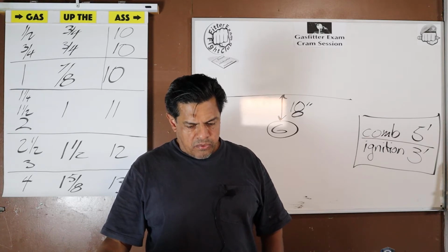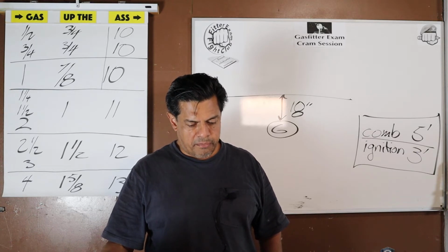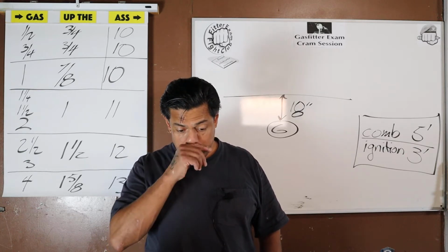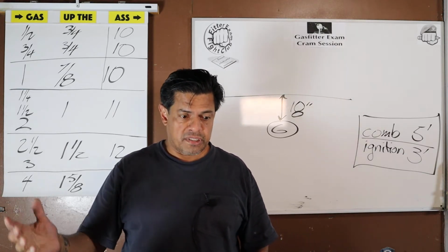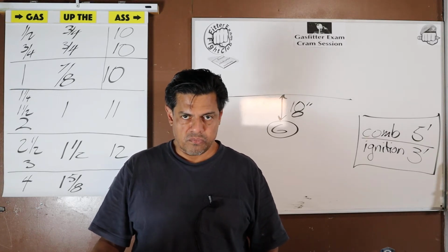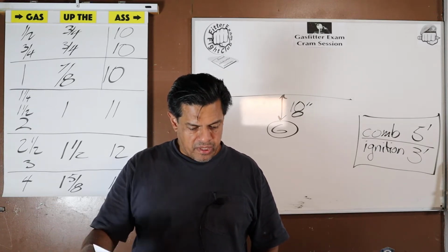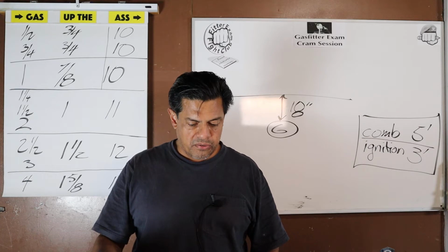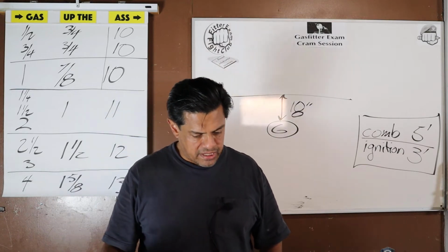So one of the things is, if properly protected. Question 31 shows another thing they were worried about. If we're going to install gas piping less than 2 feet below the ground, it shall be protected against frost, and this harkens back to outside meter piping, unless it's certified dry gas. If it's certified dry gas, which it will likely be, we don't have to worry about that. If it is wet gas and it's less than 2 feet below the ground, they're asking you to protect against freezing. So wrapping it up, insulating it.